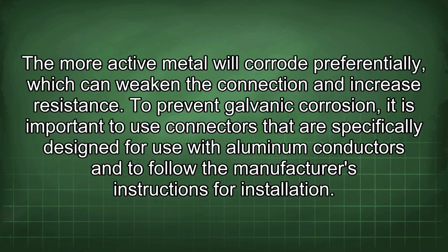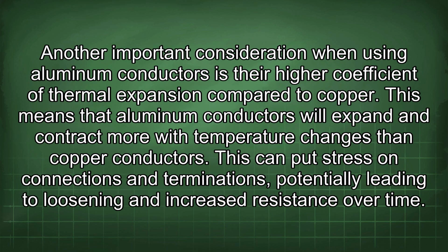To prevent galvanic corrosion, it is important to use connectors that are specifically designed for use with aluminum conductors and to follow the manufacturer's instructions for installation. Another important consideration when using aluminum conductors is their higher coefficient of thermal expansion compared to copper. This means that aluminum conductors will expand and contract more with temperature changes than copper conductors. This can put stress on connections and terminations, potentially leading to loosening and increased resistance over time.